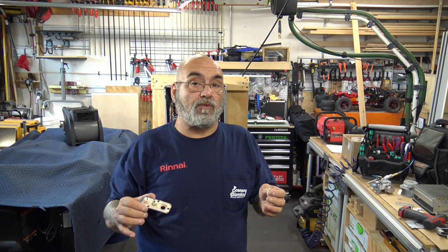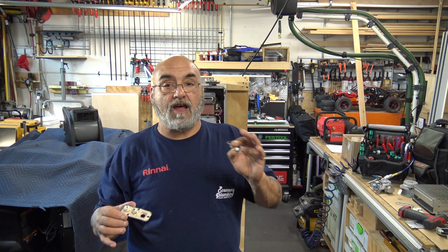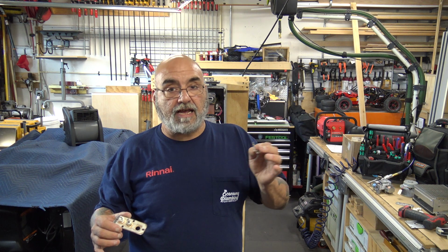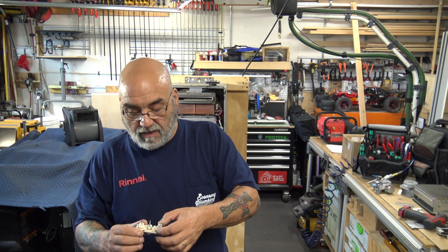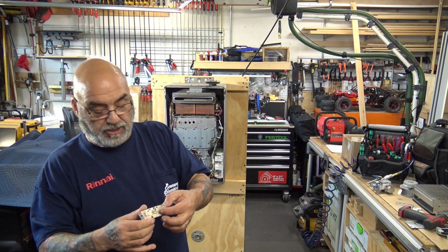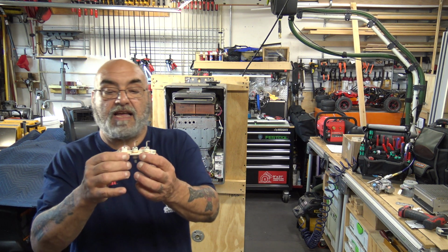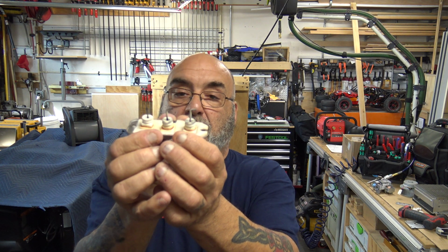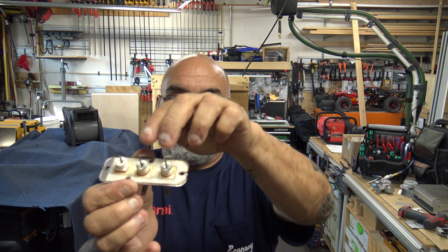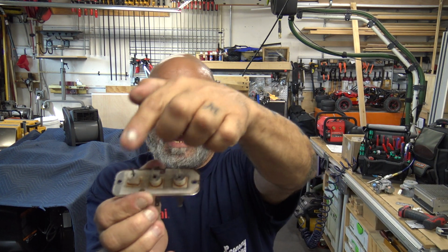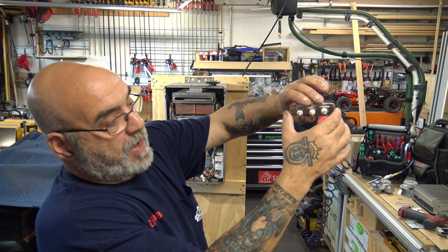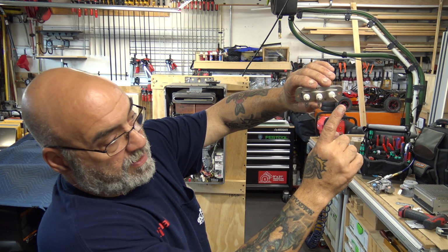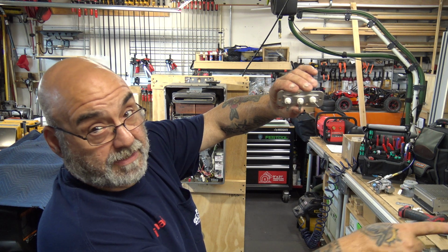So you can try cleaning this off with like Scotch-Brite or a little bit of emery cloth or very fine sandpaper. No file, no knives, no screwdrivers, no pliers, nothing—only use Scotch-Brite or an emery cloth. Just remember the orientation, that's how they sit in the burner: looking into it, the two flame sensors go to the left and the igniter goes down, which then on the bottom, the two connectors go down and the igniter goes towards the right.